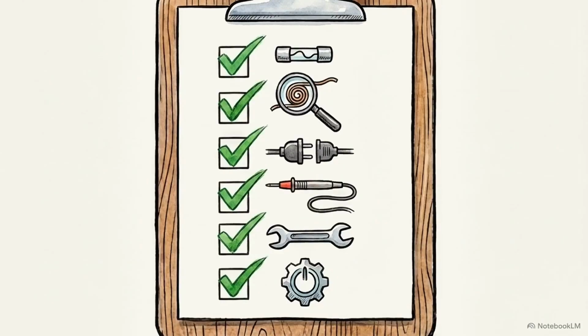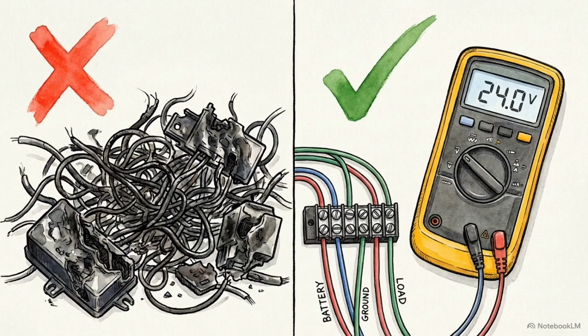This checklist summarizes the discipline. Confirm fuse size, inspect wiring, disconnect loads, test each branch individually, repair the fault, and run all modes. Systematic isolation beats guesswork on every single service call.